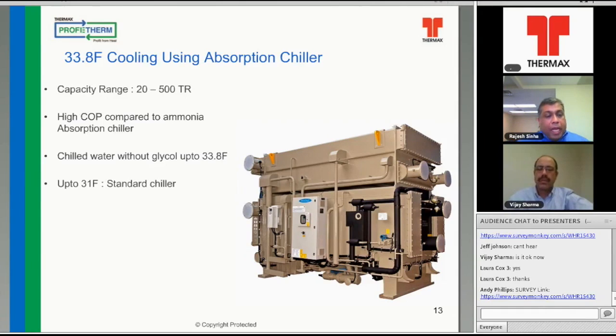Chilled water at 33.8, mind you, can be done without glycol, and below that we can go even lower using glycol or brine solution. So we actually have absorbers which are doing 31 degree Fahrenheit as a standard chiller.